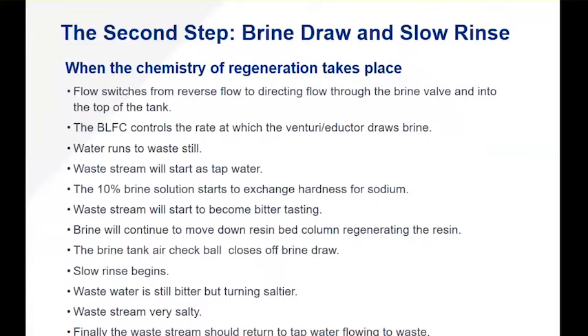You can measure this with a salometer, which is a measuring tool for measuring salt density. The old-school guys would just taste water every five minutes coming out of the waste stream — it's going to go from tap water to being really bitter because calcium, magnesium, and iron have a real bitter mineral taste, and then it'll start to mix back in with salty, get really salty, and then that saltiness will ebb back into tap water again. That's the path you want to follow to make sure you're brining properly.